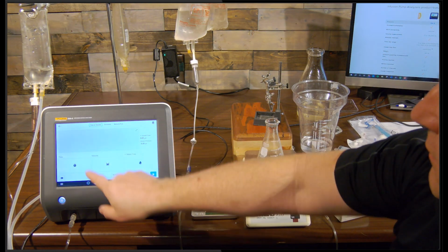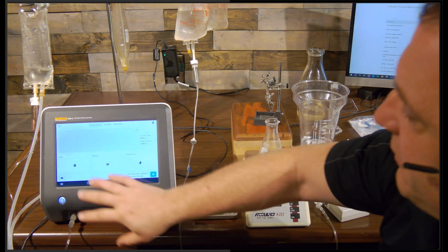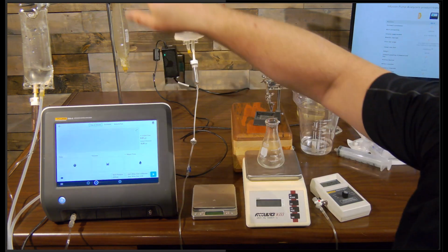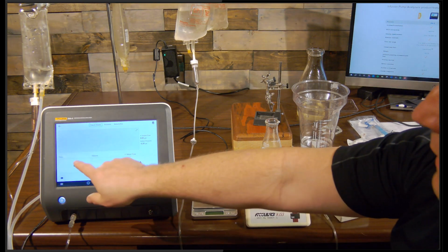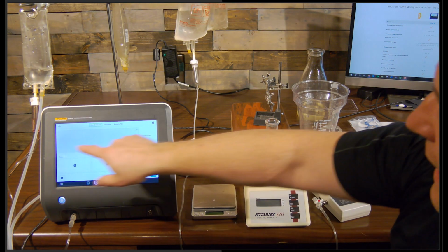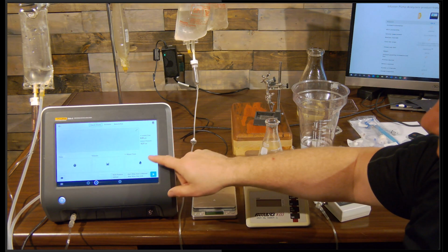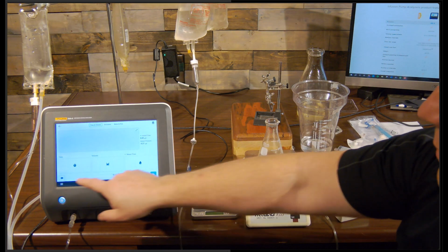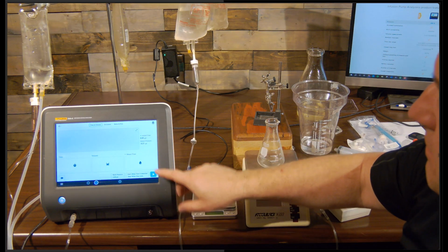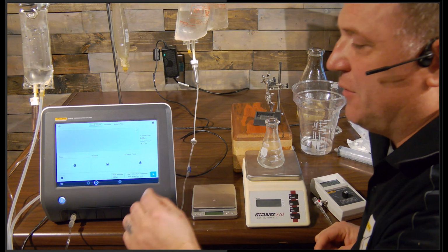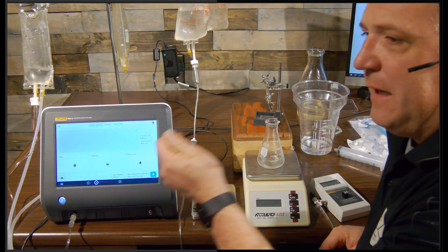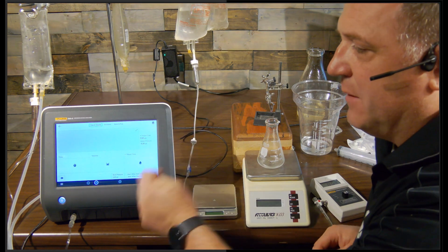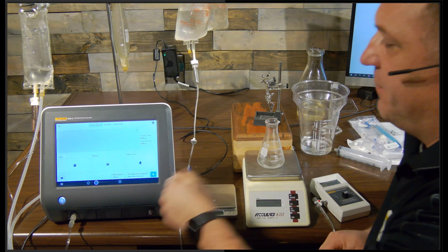I would go to flow and volume. I would run my priming cycle, push play, run my flow test. And then I'd have my volume, my average flow, and my peak flow all right here on the screen. It'll pull them all up here on my screen for me. And it's high resolution. Remember when I showed you with the syringe? It's going to read to 1,000th of a milliliter or 1,000th of a gram, depending on which way you want to measure.